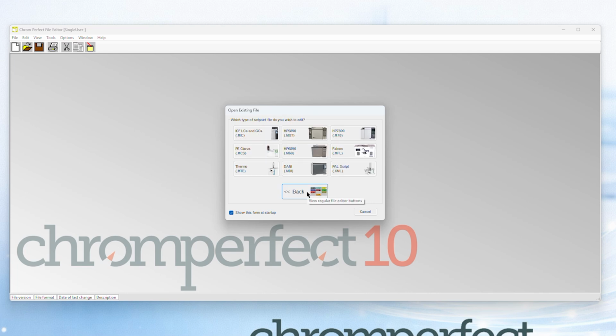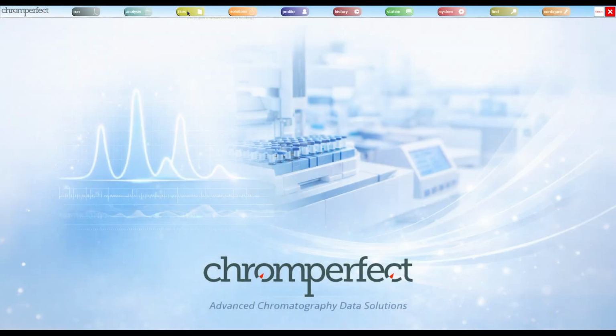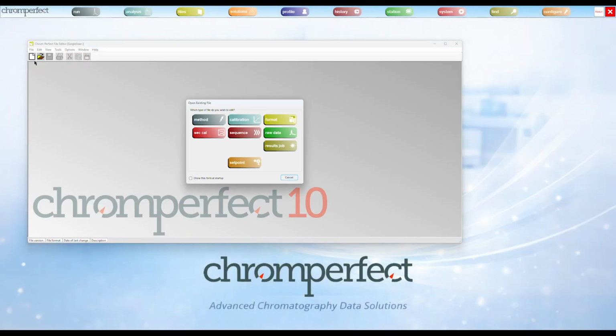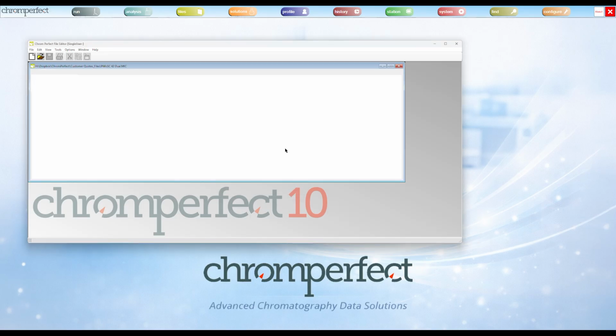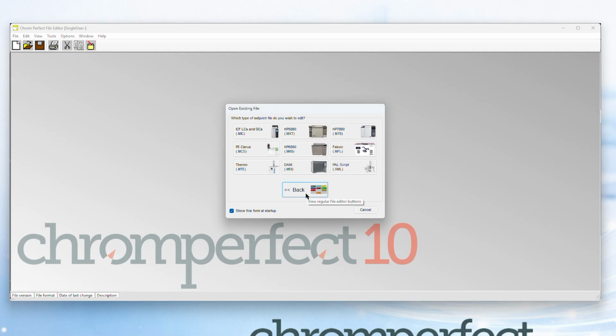So, if someone tells you to open the MIC Editor, the M78 Editor, the 7890 Setpoint File Editor, or simply the Instrument Setpoint File Editor, the practical instruction is normally the same. Open Chromperfect File Editor, choose File, Open, select the appropriate setpoint file type, and then open the relevant file.